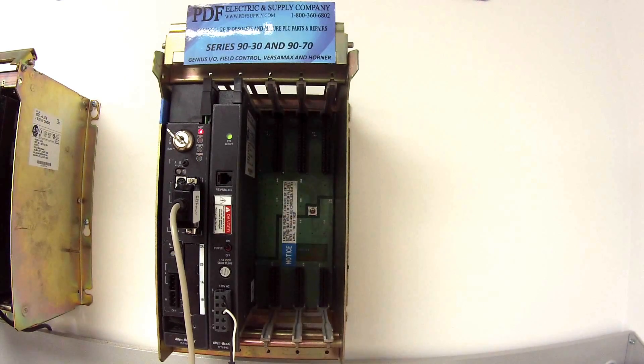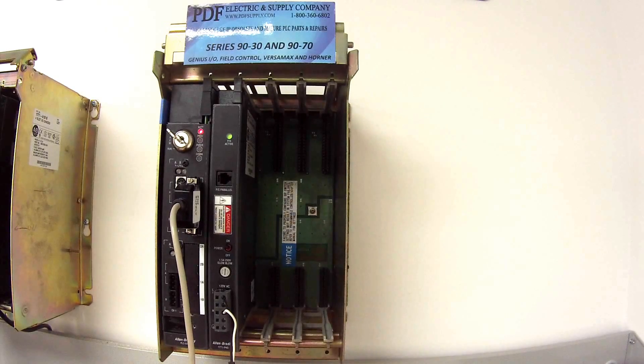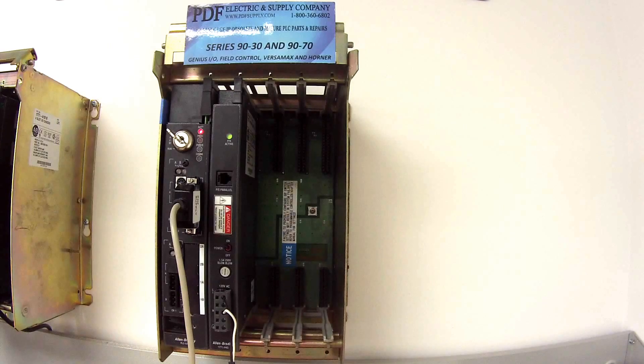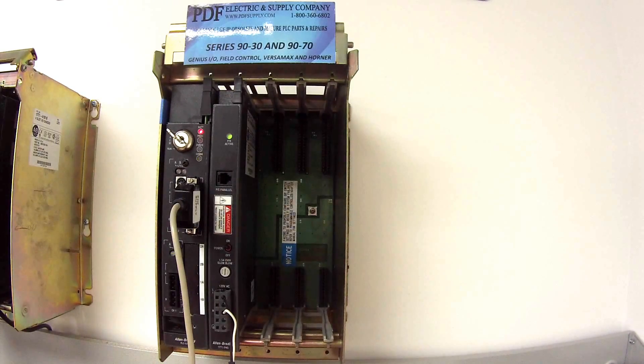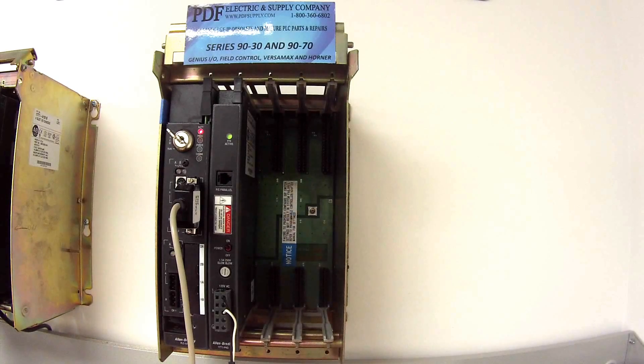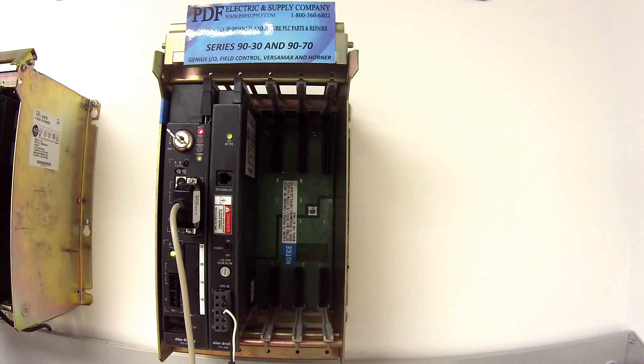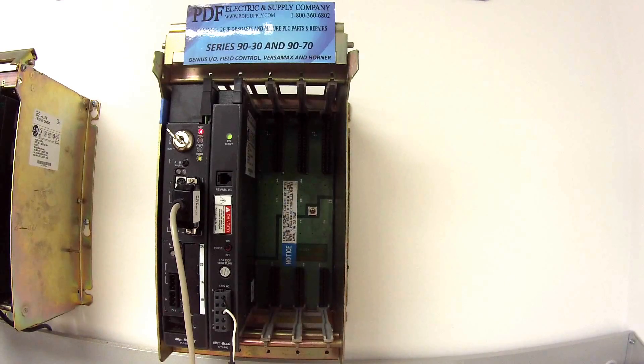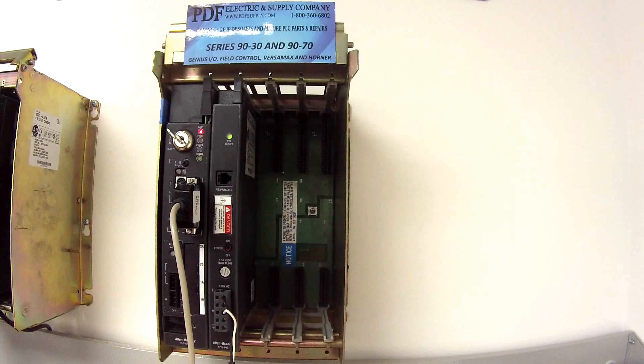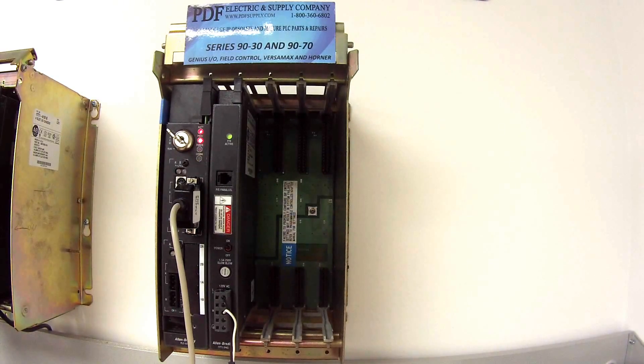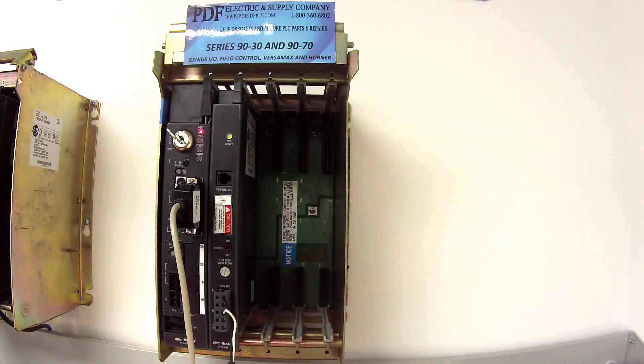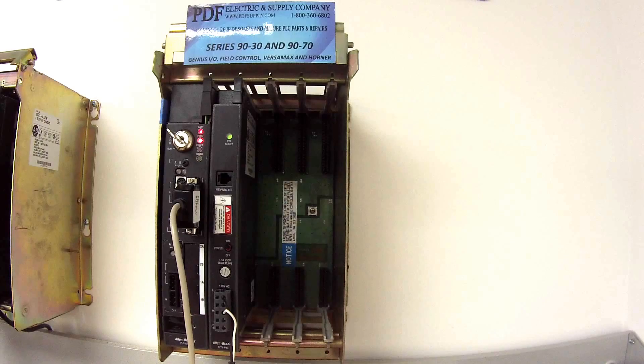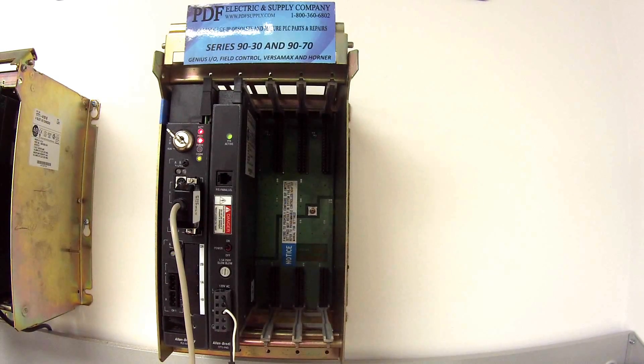So right away, it's giving me that this Series A, Rev B is not particularly the case. And mine's a Series E, Rev F. So I'm going to go ahead and select OK. And I'm selecting OK to change that. And it's going to resize my data tables. This is just what I mentioned before. That may come up if you don't select the exact Rev and Series. It'll select it for you. Then you can go ahead with that. Next it's going to be downloading processor image. That'll take a few minutes.